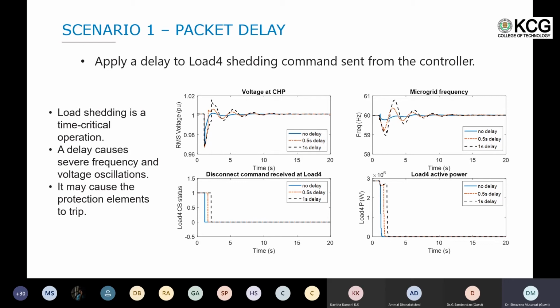Now if I add a 1 second delay, the microgrid controller observes the island happening, detects it, and sends a packet of information to load 4, but the intruder added a 1 second delay to that packet. You can see the frequency excursion—just because of that, the oscillations increase significantly.